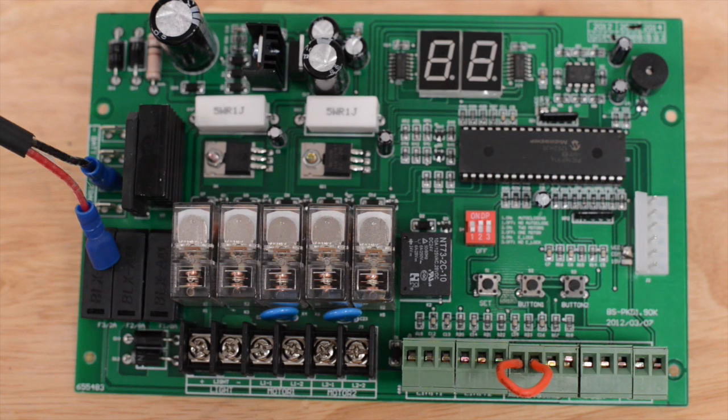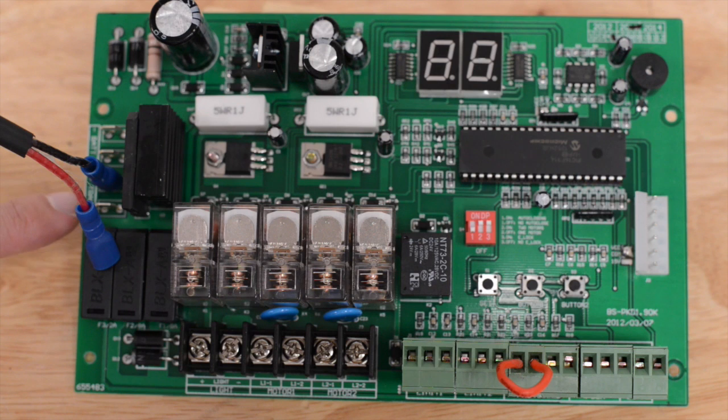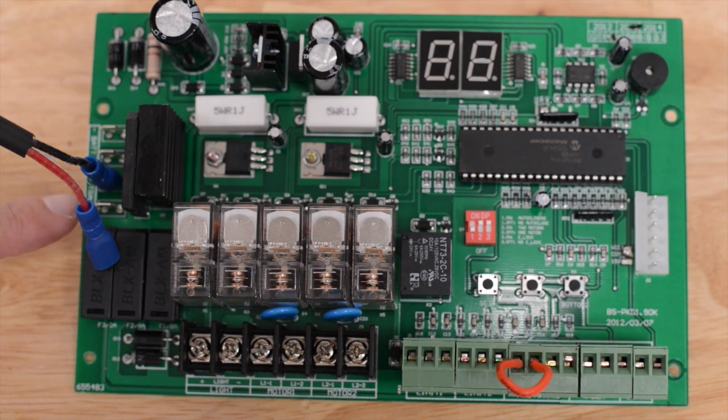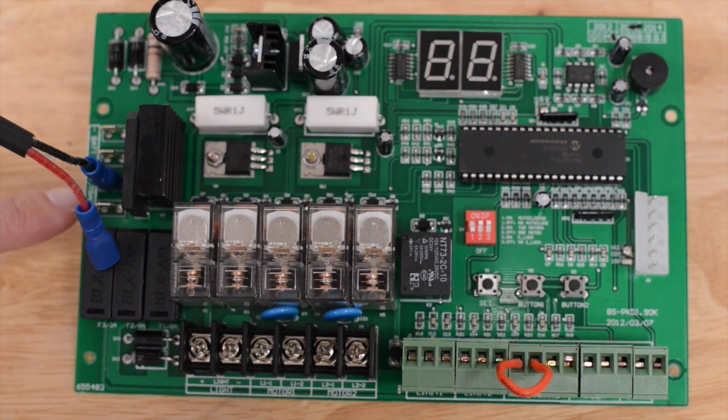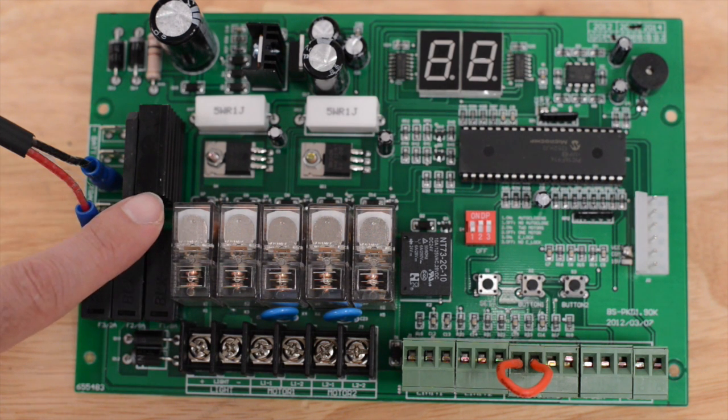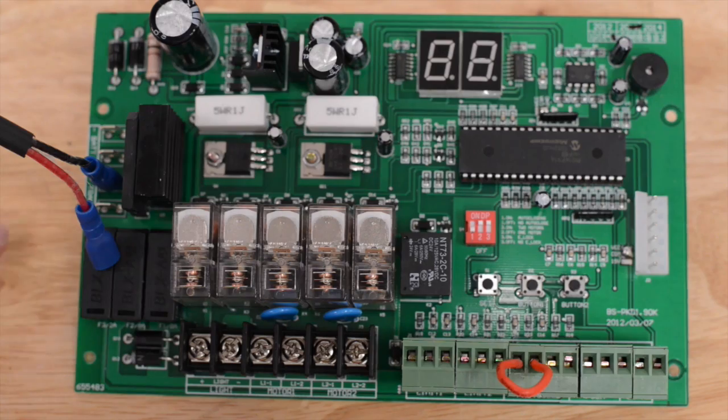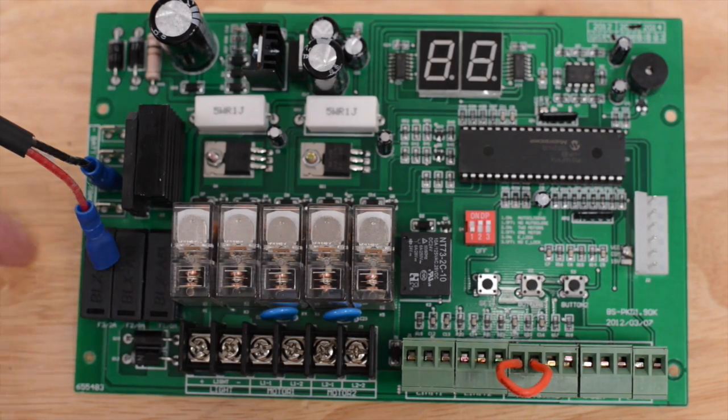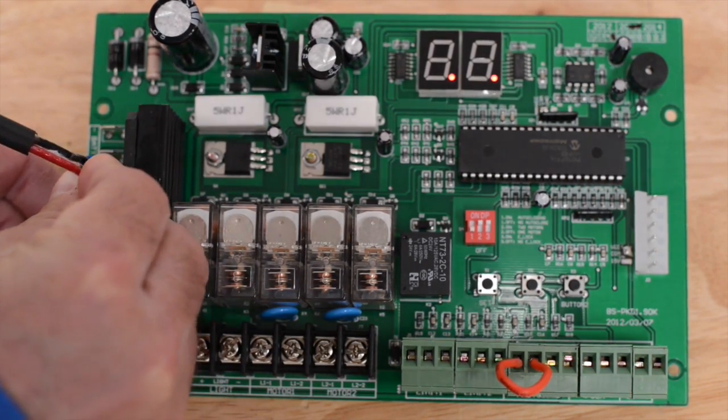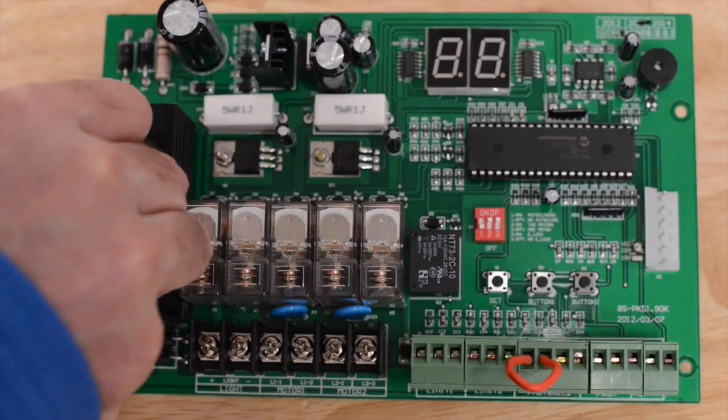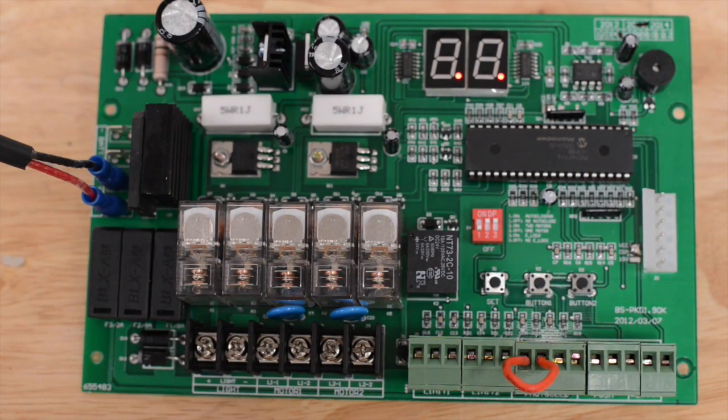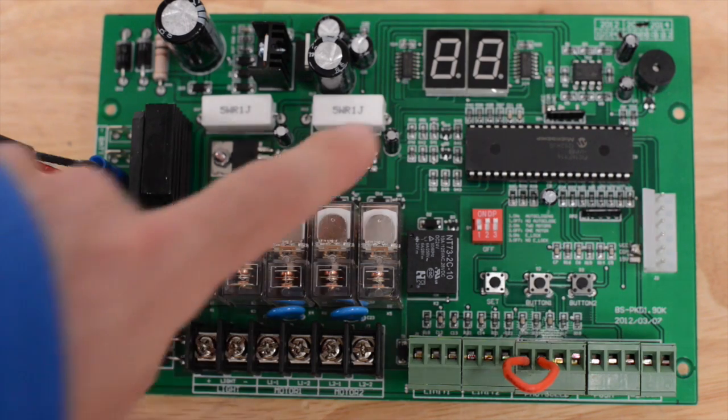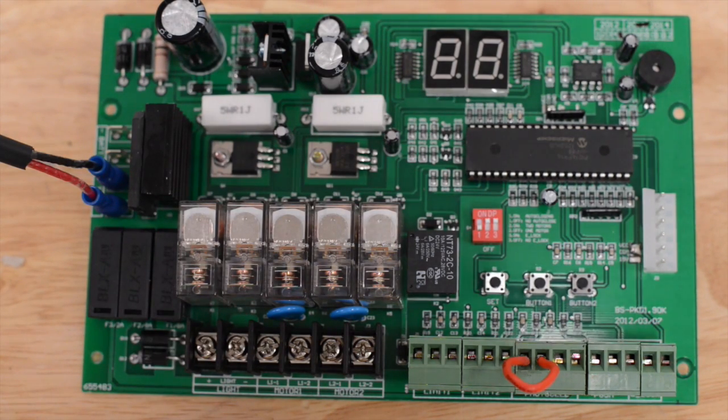The only power that is required for this control board is the TRAN. The transformer is a 24-volt, 50VA, AC transformer. It reduces 120 volts AC to 24 volts AC. It does not convert it to DC. This is the DC converter. I'm going to plug in the incoming power. Note you should hear a beep when you plug in the power. Lights will blink temporarily and then turn off.